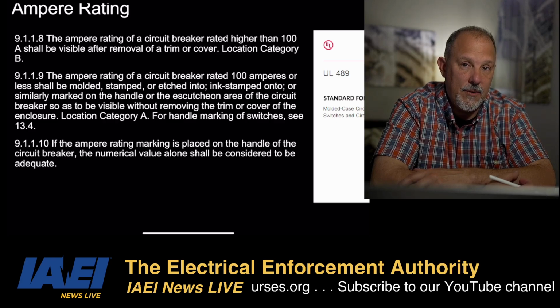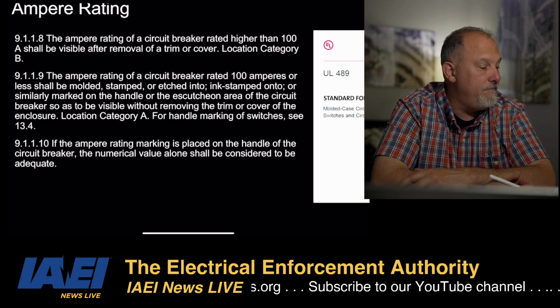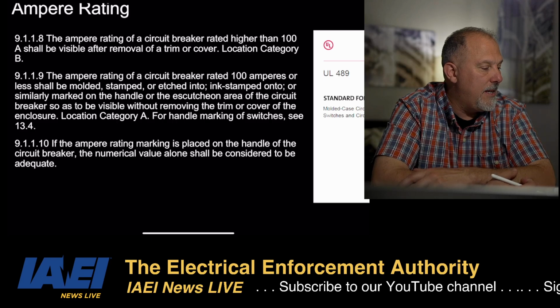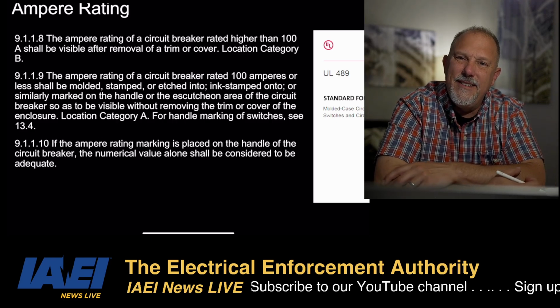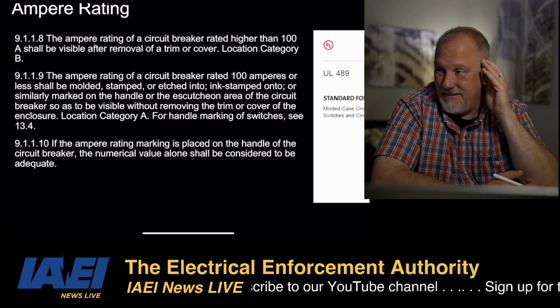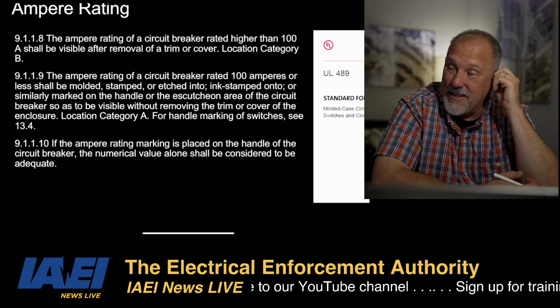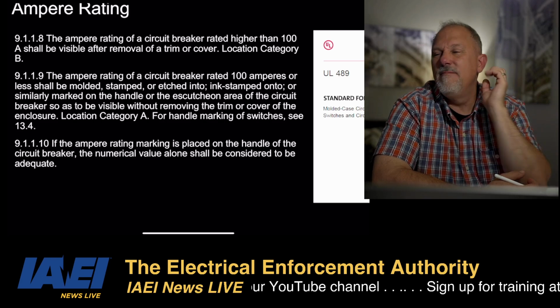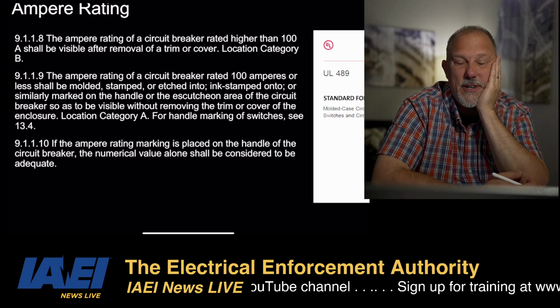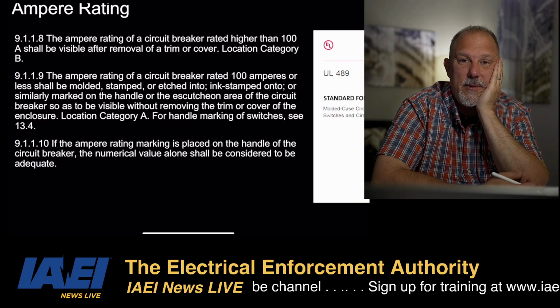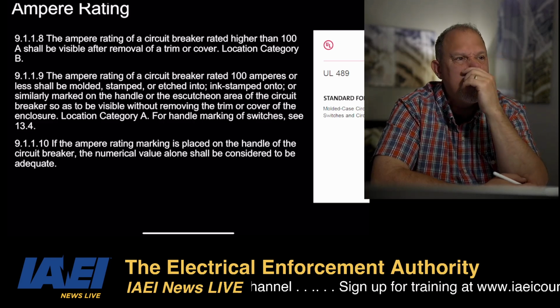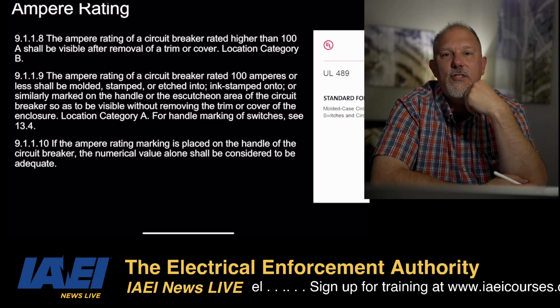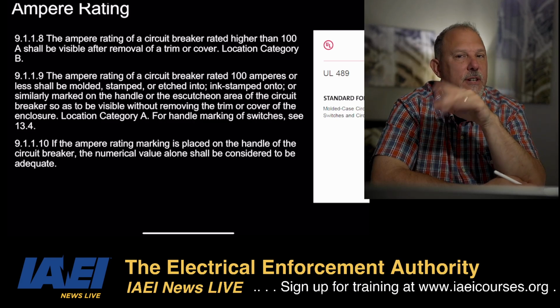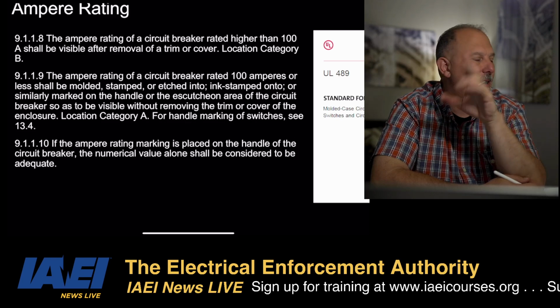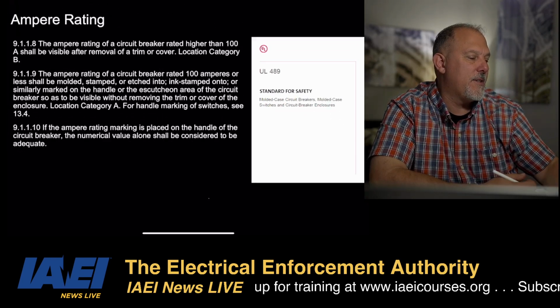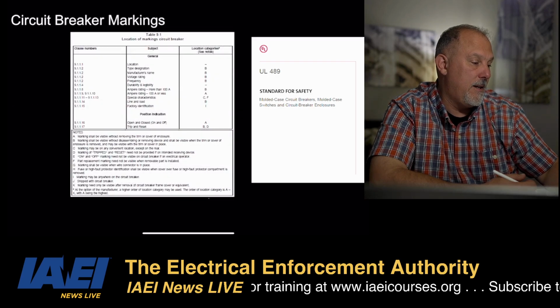That is going to be greater than 100 amps. Which doesn't make sense to me. Think about it. Do I want to remove a dead front on a large breaker to see what the Ampere rating is? Now, most of those are going to have electronic trip units and all that jazz, and you're going to have all that information through the... I don't know. What are your thoughts on that one? Love to know.